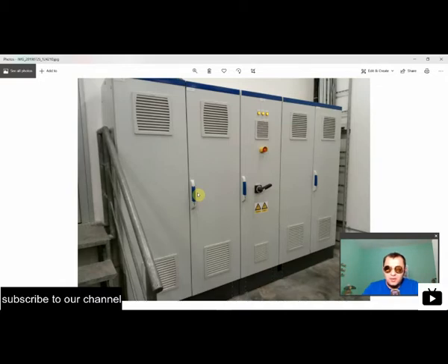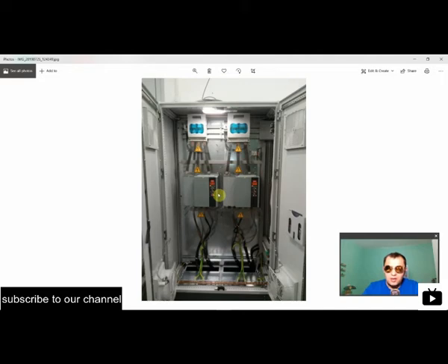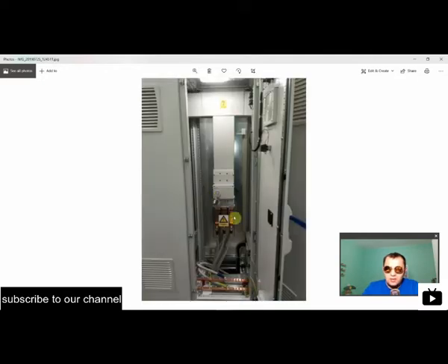And this PDF document with all the power consumers and all the control equipment, from this point on I could design this whole system completely on my own. I got all the part numbers, all the data from the manufacturer, so that was great. We had to, of course, dimension the soft starters accordingly for driving the compressors. I also had to dimension the power distribution system. As I said, we had about 400 kilowatts of power consumption, and for that we had to dimension the power supply cable and also the busbar system.